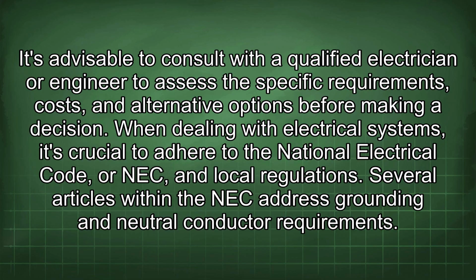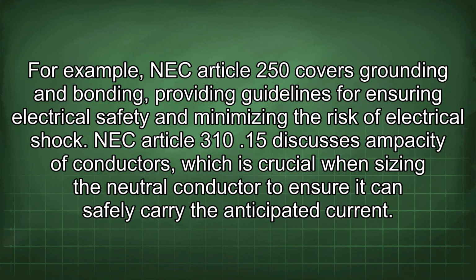making a decision. When dealing with electrical systems, it's crucial to adhere to the National Electrical Code, or NEC, and local regulations. Several articles within the NEC address grounding and neutral conductor requirements. For example, NEC Article 250 covers grounding and bonding, providing guidelines for ensuring electrical safety and minimizing the risk of electrical shock. NEC Article 310.15 discusses ampacity of conductors, which is crucial when sizing the neutral conductor to ensure it can safely carry the anticipated current.